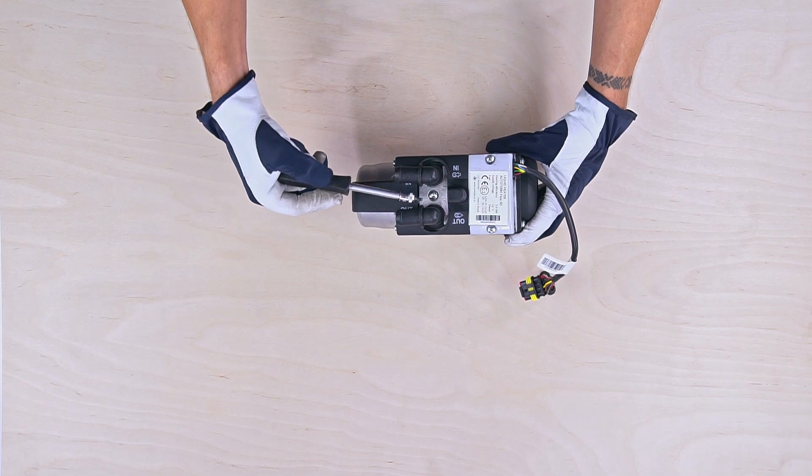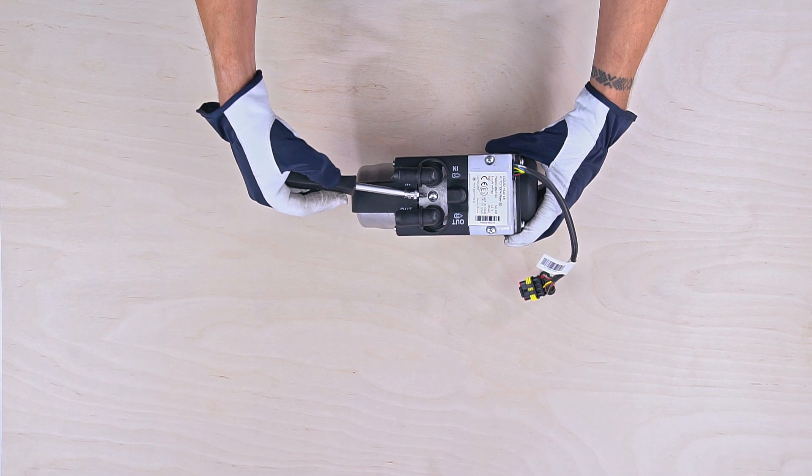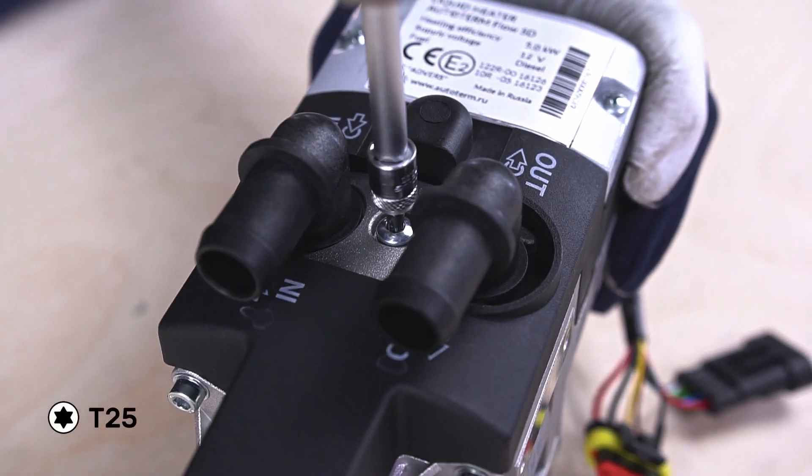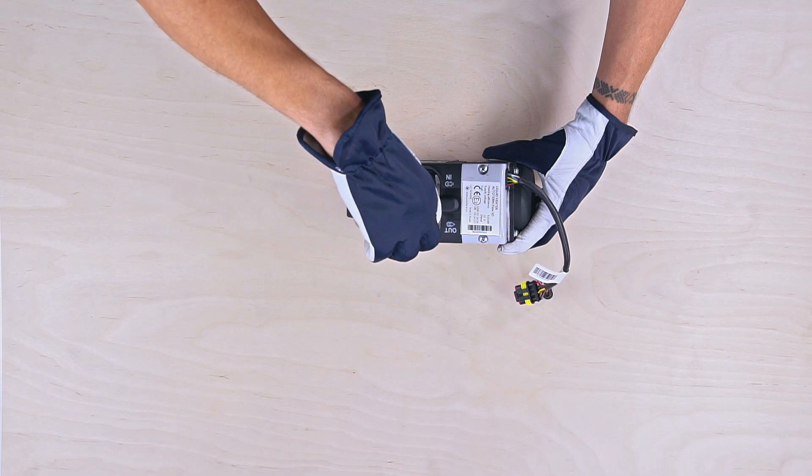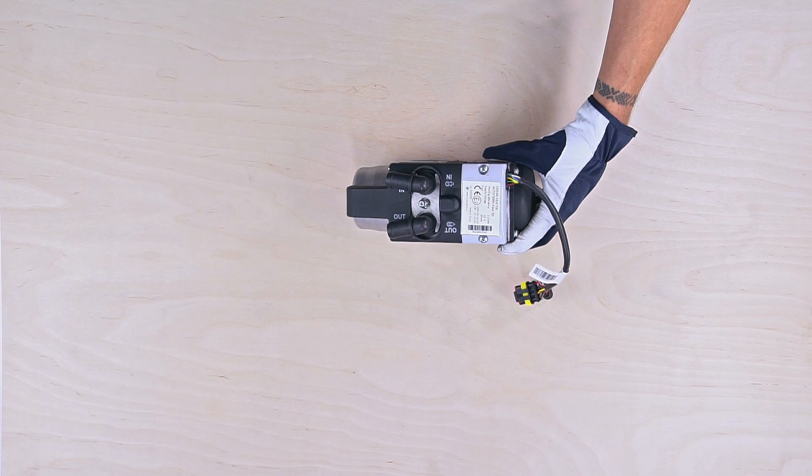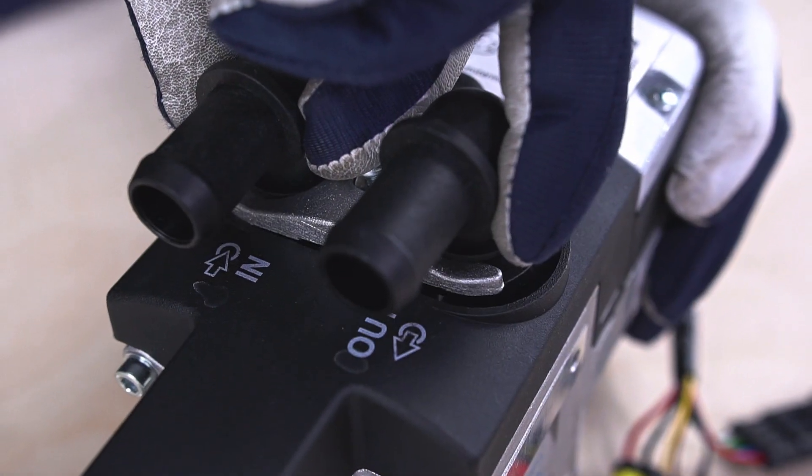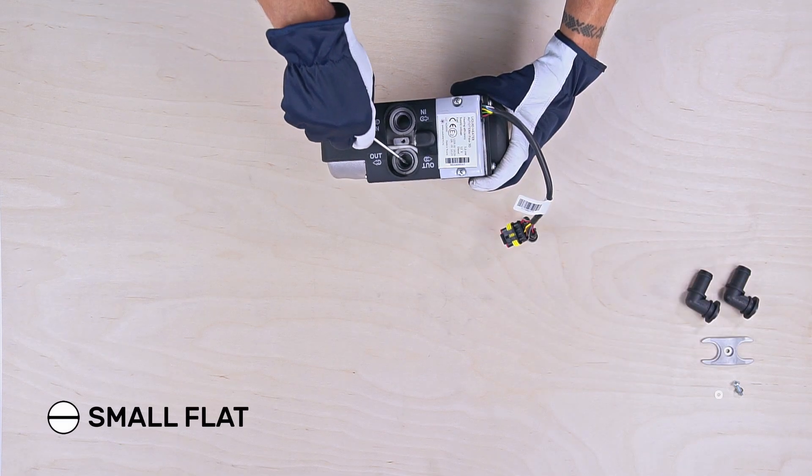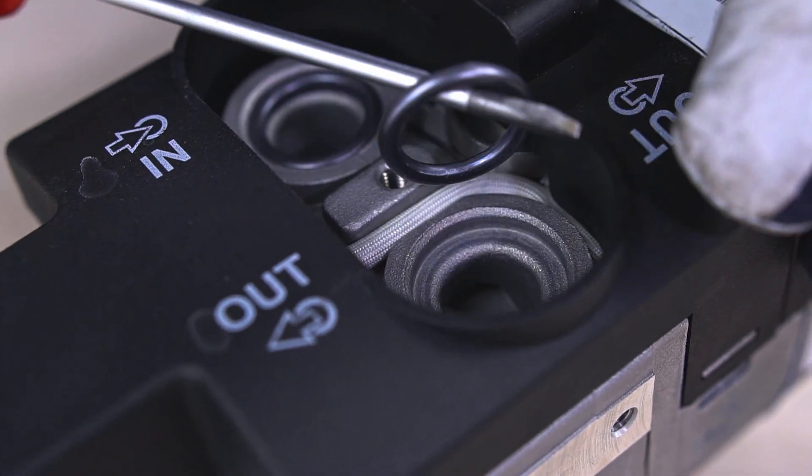First we are going to remove the coolant input output elbows. Using the Torx T25 key, unscrew the bolt between both coolant elbows. Take both coolant elbows off. With a small flat end screwdriver, remove both sealing o-rings.